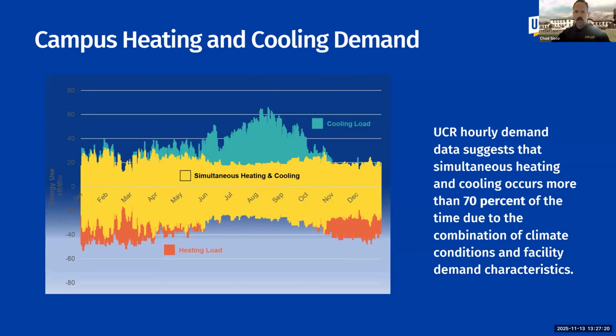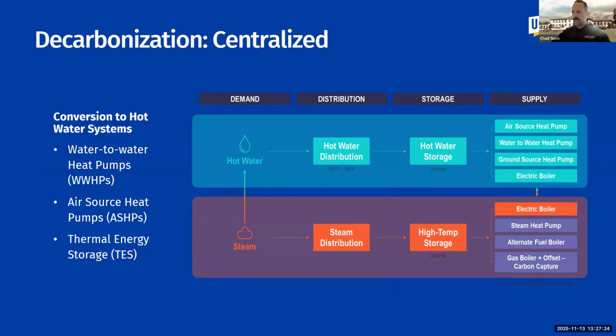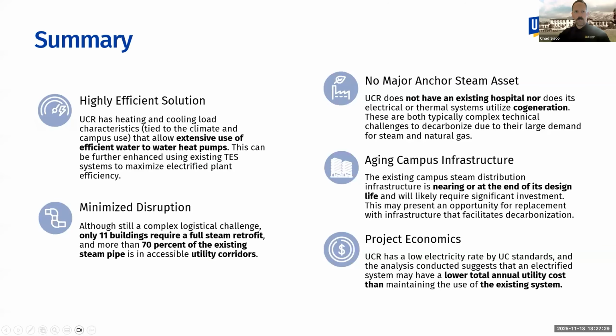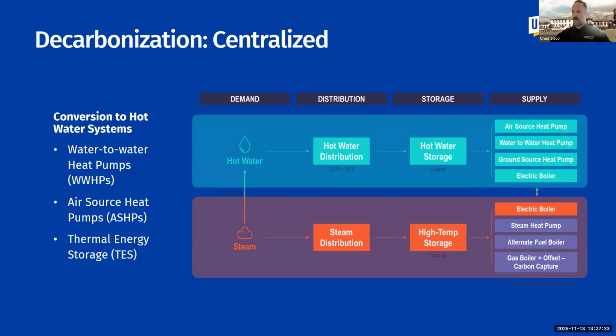So moving forward with decarbonization, a total of 5 major scenarios were explored in our study compared to the business as usual scenario. Some of them included variants. Scenario 1 involved electrification of the existing steam plant enabled by building and distribution transitions from steam to low temperature hot water. The variants 1.1 and 1.2 are just with and without hot water thermal energy storage. Scenario 2 studied breaking the central plant into heating districts across the campus. 3 looked at electrification of the steam boilers. 3.1 and 3.2 compared electric boilers versus heat pump. Scenario 4 explored alternative fuel options, including biomethane and hydrogen. And 5 studied the actual decentralization of the campus and electrifying it at the building level.